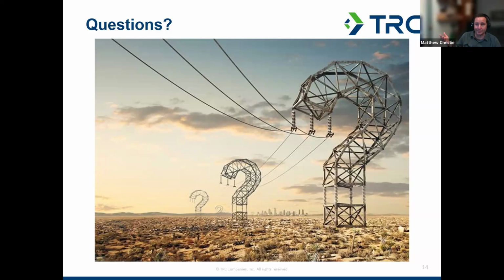If you can go without that, you can avoid one of the biggest loads when you're doing heat pumps, which is electric resistance backup or electric resistance complement to your heat pump load. But yeah, when heat pumps are actually running most of the time, it's 2 amps, 1 amp, super low. They might spike to higher amperage on startup, but that's not what the NEC calculation cares about or takes into account, because it has to be sustained is the question.